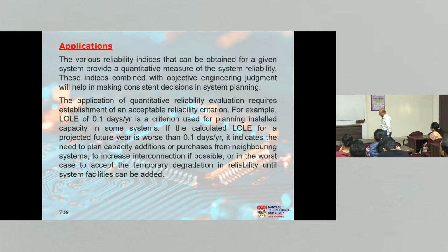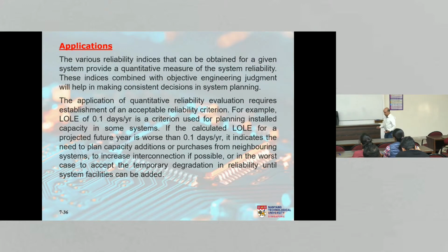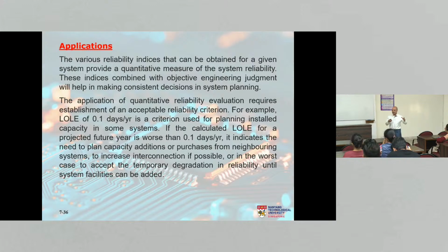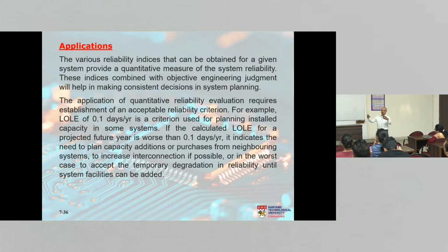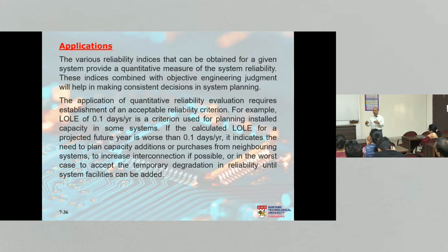Just summing up now, the applications of generating capacity reliability evaluation. We have seen how to calculate the reliability indices. We have the capacity model, we have the load model, we convolve the two, and we get the risk model. We also know how to do sensitivity studies. We can change the peak load, change the unavailability of the generators, include uncertainty, include maintenance. In fact, we can add generators and remove generators. I did not show you the recursive algorithm for removing generators, but it is actually the same equation, except that you rearrange it for unit removal. So there are many things that one can do.